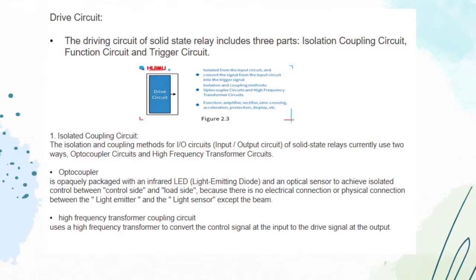And next is the high frequency transformer coupling circuit, which uses a high frequency transformer to convert the control signal at the input to the drive signal at the output. So the detailed process is the input control signal produces a self-isolating high-frequency signal that will be transmitted through the transformer to the transformer secondary, and after the process by the detection or the rectification circuit and the logic circuit, the signal will eventually become the drive signal to drive the trigger circuit.